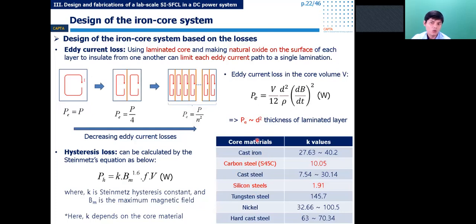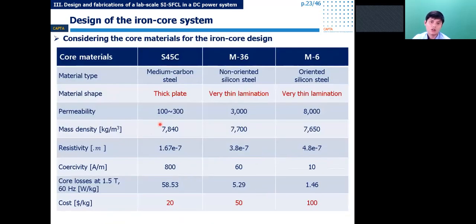In the first step, the iron core was designed to minimize the eddy current loss and the hysteresis loss. The laminated structure was selected to minimize the eddy current loss. In the case of the hysteresis loss, we can select core material like carbon steel or silicon steel to minimize it. Considering the core material and the core properties, three core types, including medium carbon steel, non-oriented silicon steel, and oriented silicon steel, were investigated and analyzed.